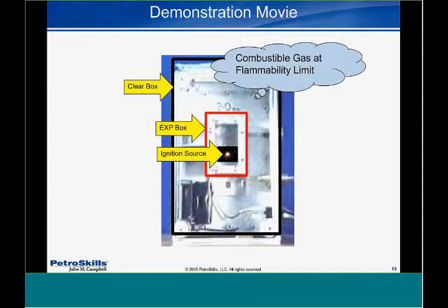So if you don't maintain these faces, if they get corroded, or you paint the faces or paint the boxes, they won't work. Once you understand how the boxes work, you can work around them more safely with other people who don't understand how these devices work.